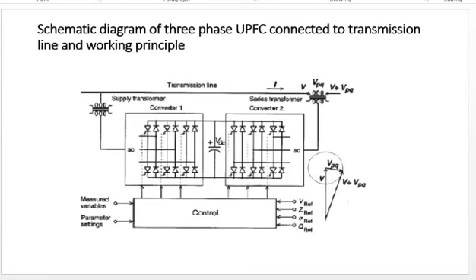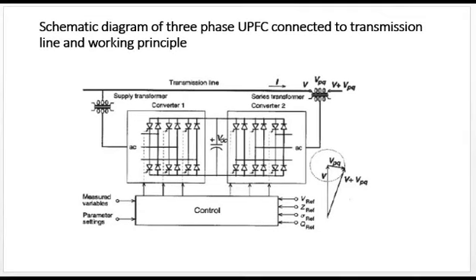Obviously, there can be no net real power flow through the UPFC DC link. If we talk about the diagram further, we can see that supply voltage Vs and compensated voltage Vpq together serve the load. The converter injects voltage in series with the transmission line, so the existing voltage is increased.